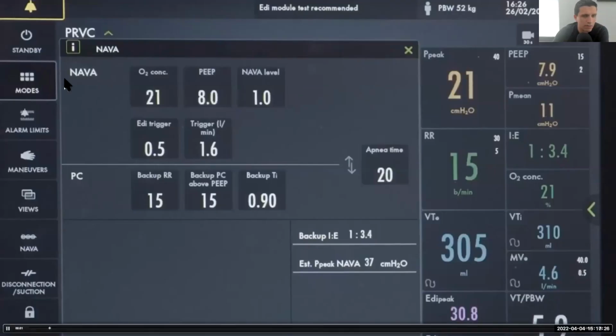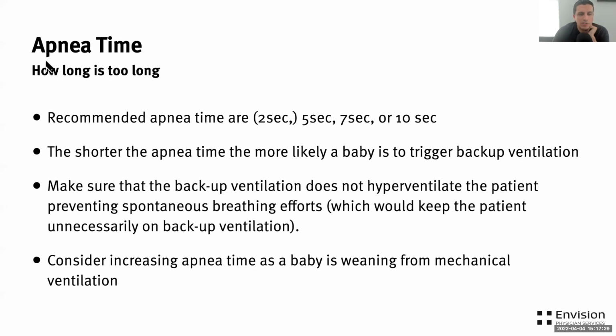Apnea time, let's see. I'm sorry, 1 second. Oh, so one of the settings you can set is the apnea time, right? That means how long I am going to tell the vent that it can tolerate the baby not making an effort. And those could be set theoretically at either 2 seconds, 5 seconds, 7 seconds, or 10 seconds. I do not recommend using 2 seconds. The reason is, as you may have guessed, the shorter your apnea time, the more the vent will trigger the backup ventilation system. Because you're saying, hey, if the baby doesn't breathe for 2 seconds, then the baby is apneic, you have to kick in regular NIMV or regular conventional ventilation.